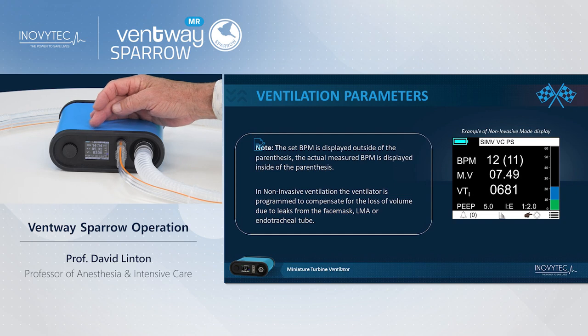If the patient is non-invasively ventilated via face mask, the ventilator is programmed, when you select non-invasive, to compensate for the loss of volume due to leaks from the face mask or laryngeal mask airway. Even if the endotracheal tube does not have a balloon and you select non-invasive, it will adequately compensate for the leak, making it ideal for ventilating patients who want to talk during ventilation, or for children in whom you do not use a balloon.